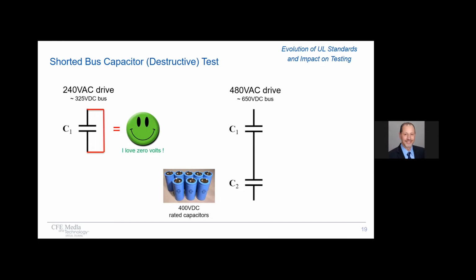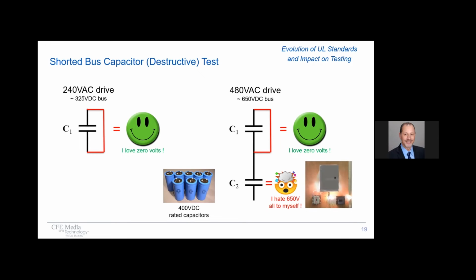But let's look at the case of a 480 volt drive. Now the rectified value there for the DC bus is 650 volts, but we're using those same 400 volt capacitors, but we use two of them in series. This is the typical architecture of a drive. And when we use two of them in series, the voltage is being shared between those two capacitors. So when we simulate a short circuit across one of the capacitors, again, that capacitor has no problem. We're taking it from an average stress situation down to zero stress. But what happens there is that that capacitor isn't taking on its responsibility anymore. And now all of that voltage, that 650 volts, is being applied across that other capacitor that's only meant for 400 volts. So the result is not very good at all. That capacitor hates having that, and the result is explosive.